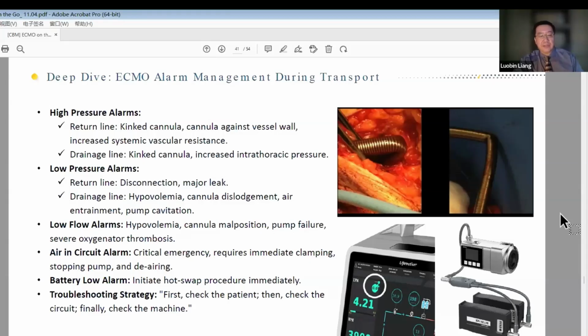And also the battery. Make sure the battery has enough power, and watch for a low battery alarm. You need to initiate a hot swap procedure to switch the battery. That's why we developed this Y cable, so you can swap the battery and at the same time continue the support. The troubleshooting strategy is you first check the patient, then you check the circuit, and finally you check the machine, making sure every step is correct. Every problem needs to be fixed during the transfer.